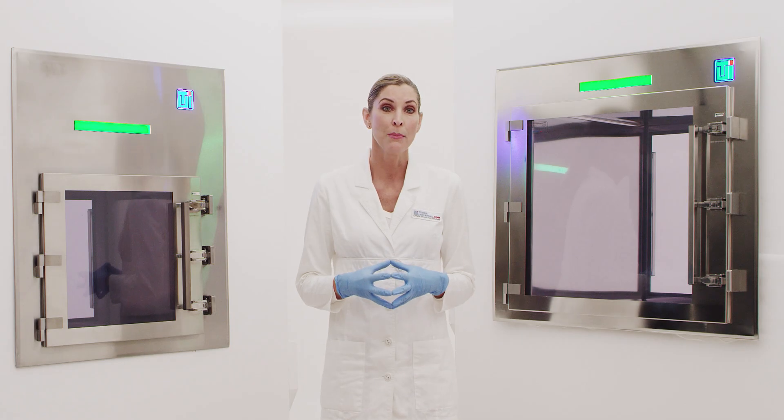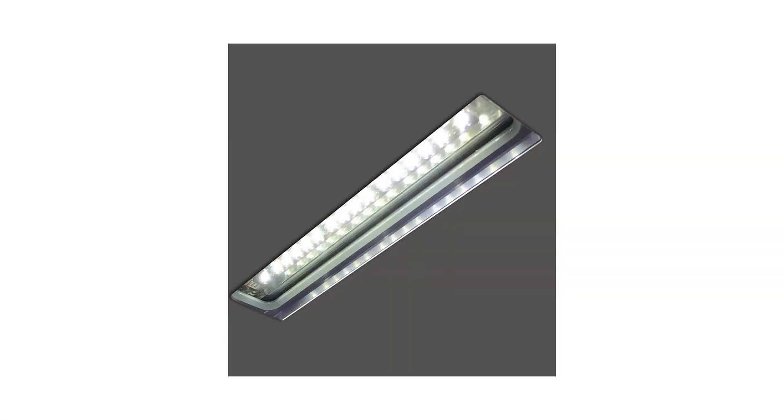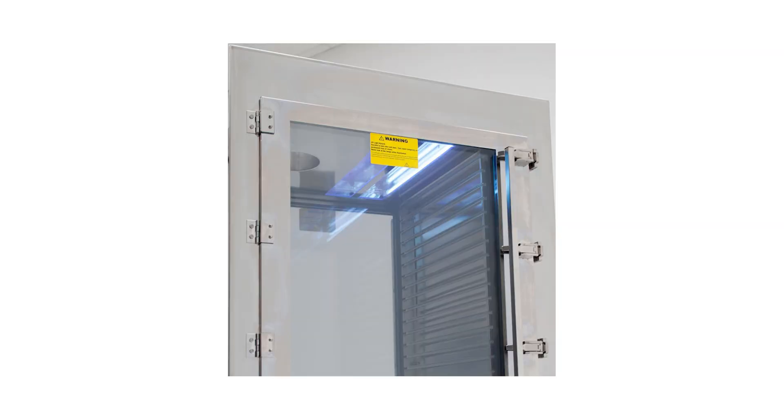Terra Universal Smart Pass-Through chambers offer several standard lighting options. LED lighting illuminates the internal chamber and mounts flush into the ceiling for easy wipe-down. The LED light automatically activates when either door is open, saving operators time during high-throughput work. Germicidal UV-C light emitted at 254 nanometers denatures microbial DNA after short, intense exposure. UV-C light is effective in disinfecting products and samples from bacterial, fungal, and viral contamination, including COVID-19.